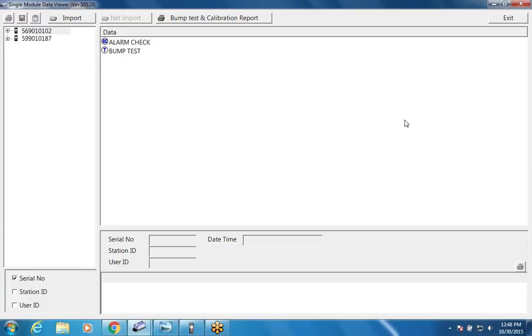If I go back, the little, what do you call that symbol? The little arrow at the bottom takes you back one screen. That's the return, yeah. So if I go into the cal screen, same thing. I can set my air time, my gas time, or my air purge time, and I can decide if I want to do an alarm check when I do a calibration, and I can decide if I want to print it automatically. So we do have the printer connected now. Oh shoot, we forgot to show that. Oh no, that's on my computer. Yeah, so sure. I'll show you what the printout looks like in a minute.